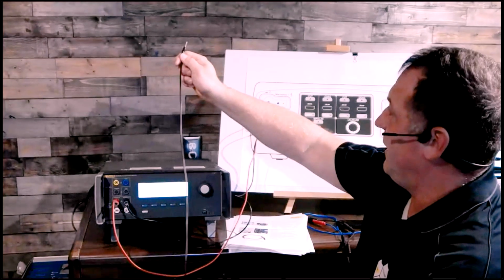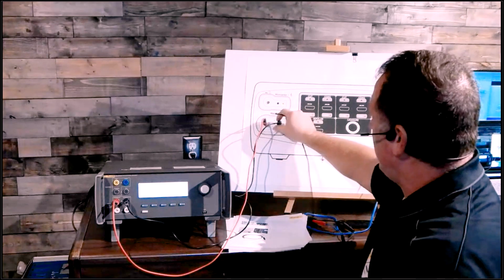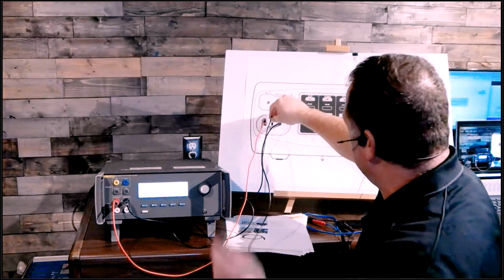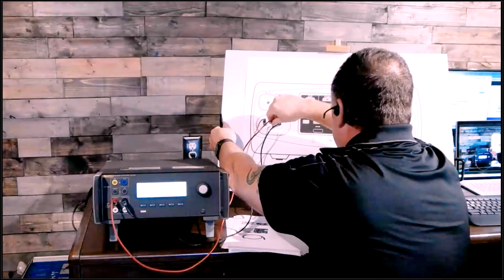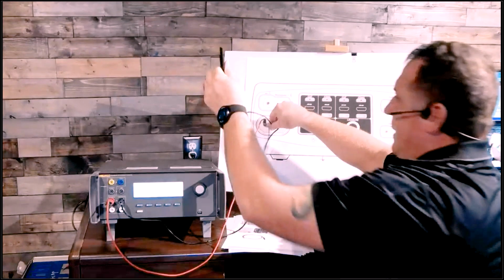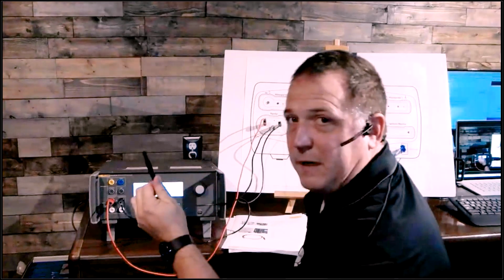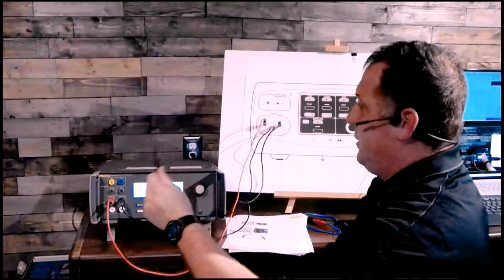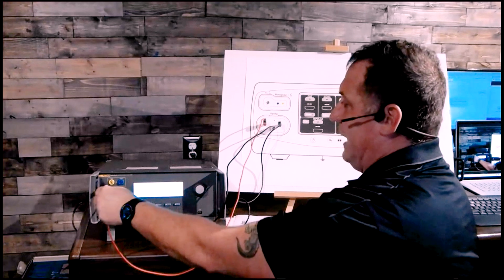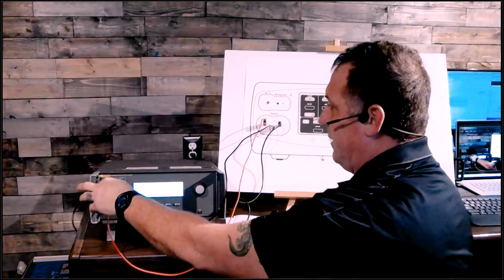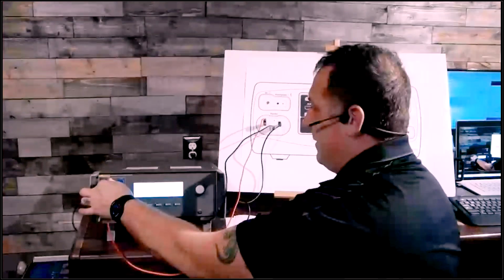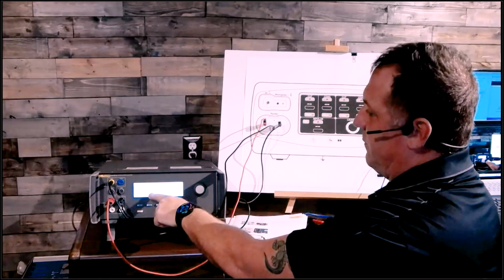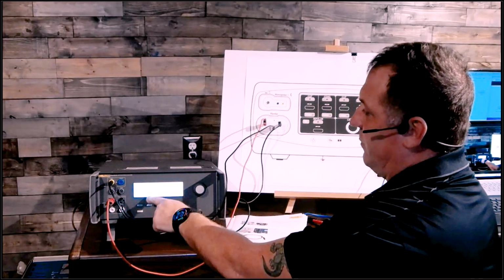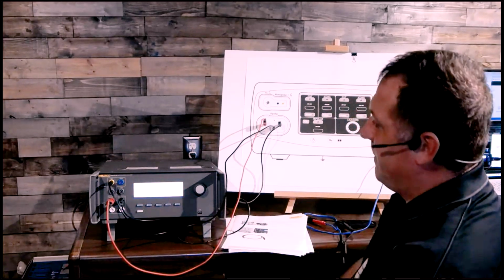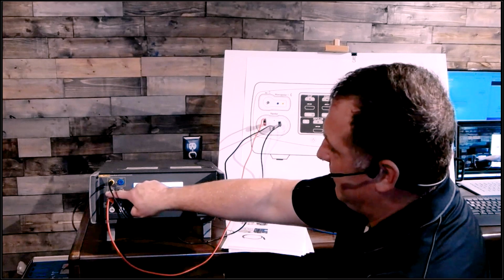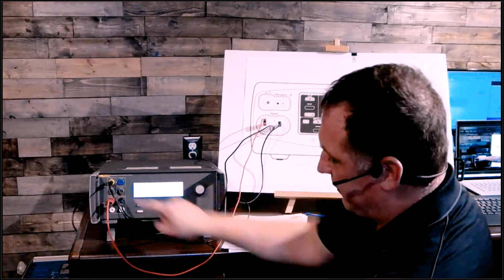We use this in that prior step with the monopolar handpiece. Those other two little ports, grab one of them, usually the bottom one, and that's where that little pin goes. Then we put this right back into the foot switch side. We can choose cut or coag, it doesn't matter which one, so let's just put this in cut. Whatever we choose here, down under the foot switch selection needs to be highlighted. So cut here, cut here. And once again, that leaves this poor common port all by itself.